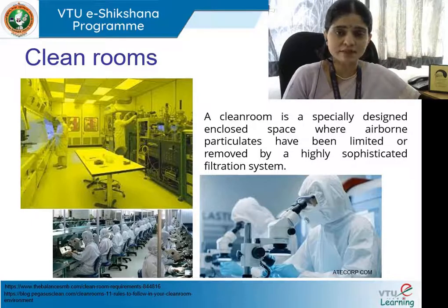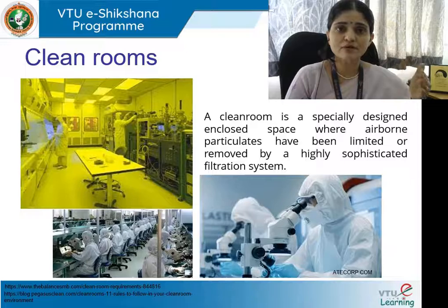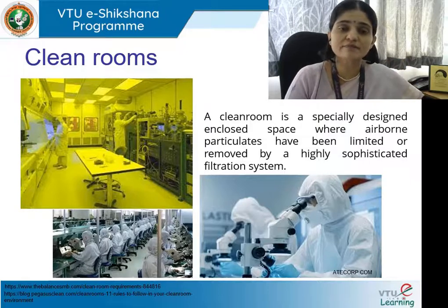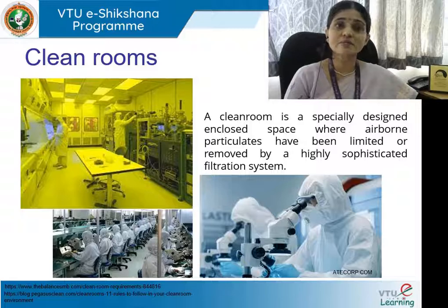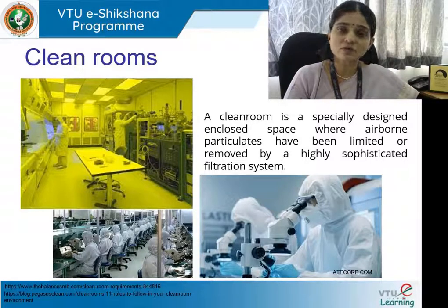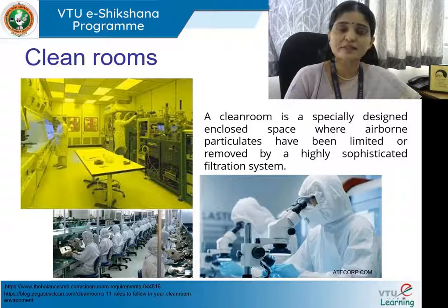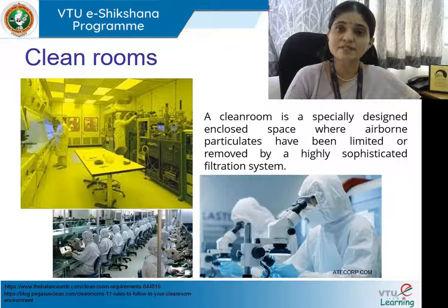In the last session we saw air filtration systems in air conditioning spaces — various types beginning with pre-filters, coarse or screen filters as the first stage of cleaning, then fine filters which are 99.9% effective, then HEPA — High Efficiency Particulate Absolute — filters, and then electronic filters. Using the highest-efficiency filtration system is advisable when designing a clean room.